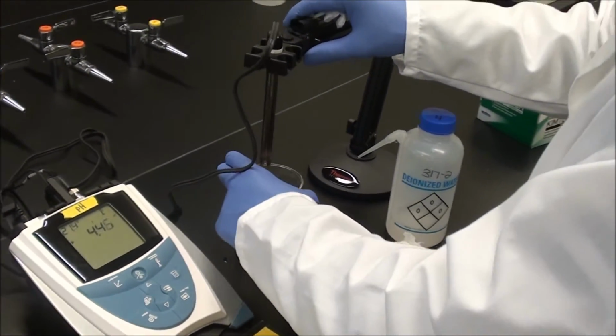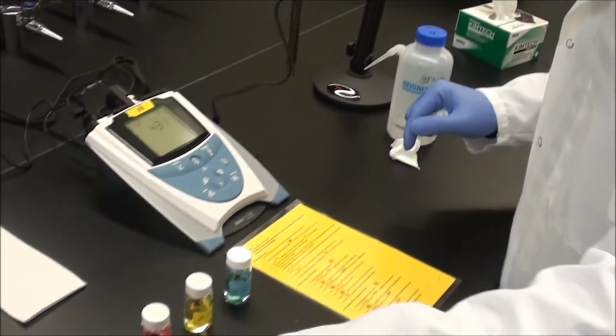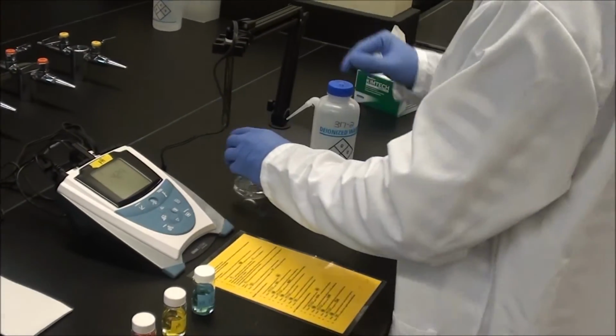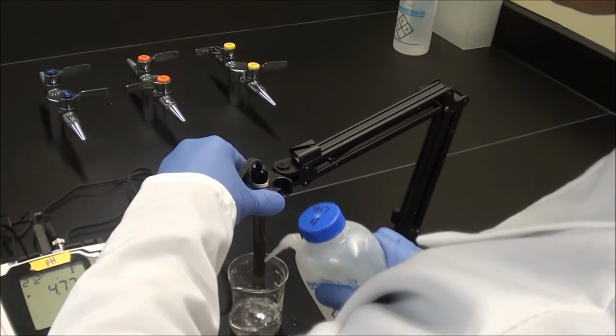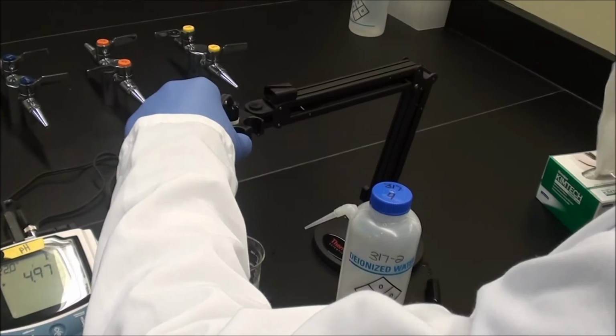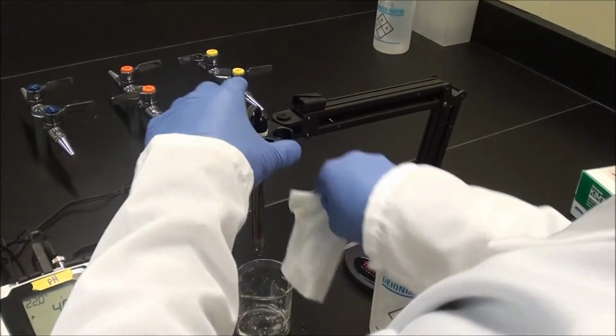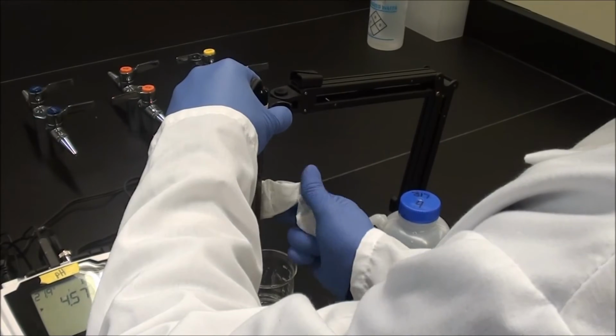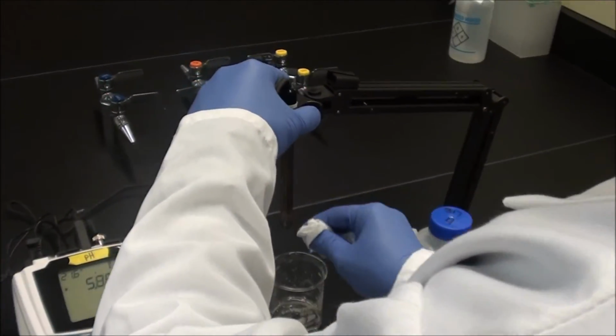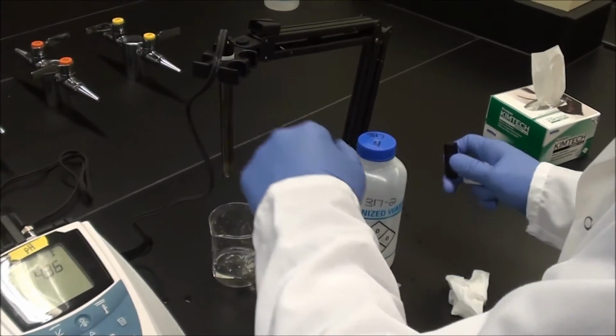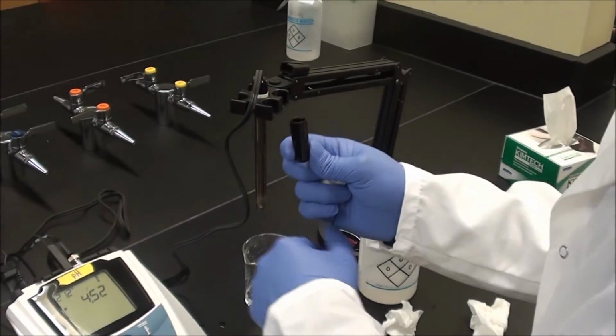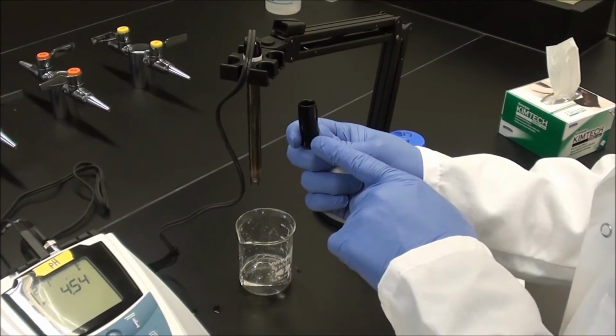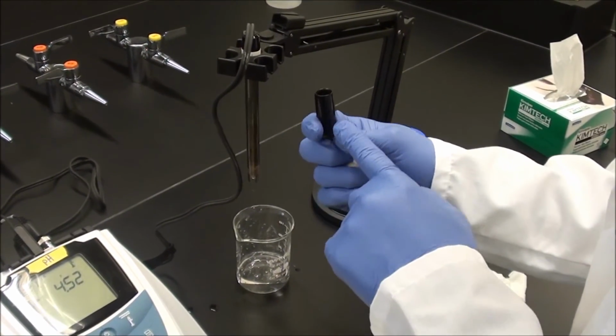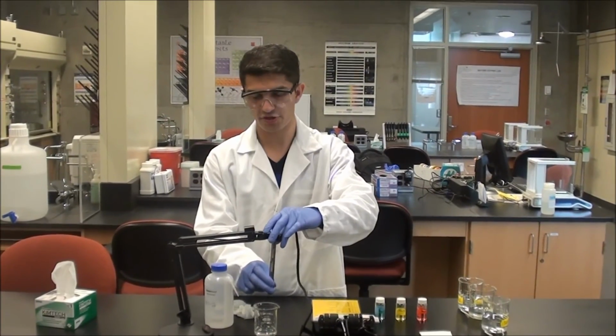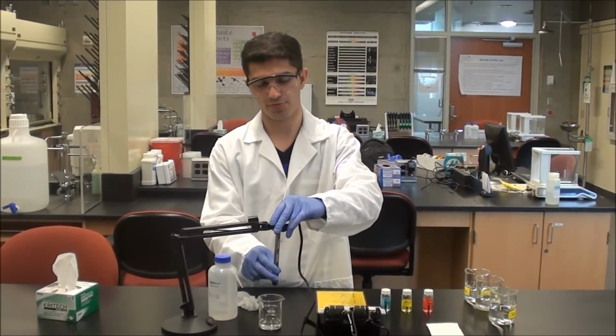I take it out of the beaker, put the DI water on the side. I want to make sure to rinse my pH probe again with DI water and wipe it with Kim wipes. And since the DI water was my last solution, I am done with my measurement, so I can go ahead and put the cap back on. But you have to make sure that you put 4 drops of pH buffer 4, which I already did. So now that you're all done, you're gonna go ahead and cap the pH probe.